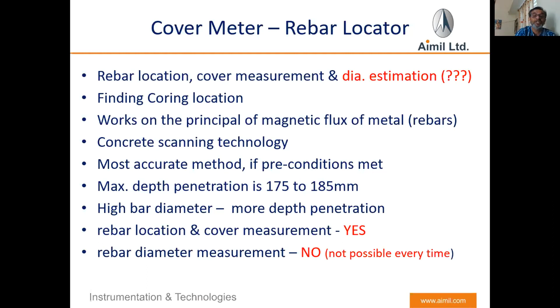location as well as concrete cover of even more than 250 mm, because with a higher size of reinforcement bar, the magnetic flux will be high and easy for the instrument to capture and detect. That's why it gives you the location as well as the concrete cover, even in case of more than 185 mm. So as I have already written, high bar diameter, more depth penetration. So rebar location, cover measurement, yes. Rebar diameter measurement, no, not possible every time.